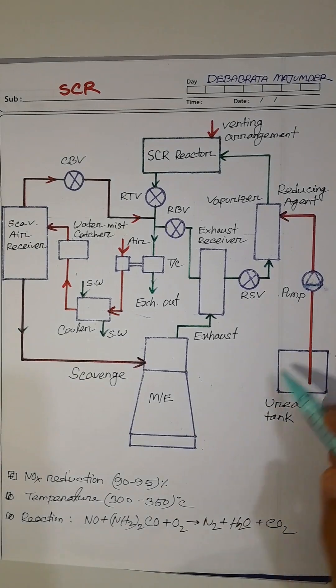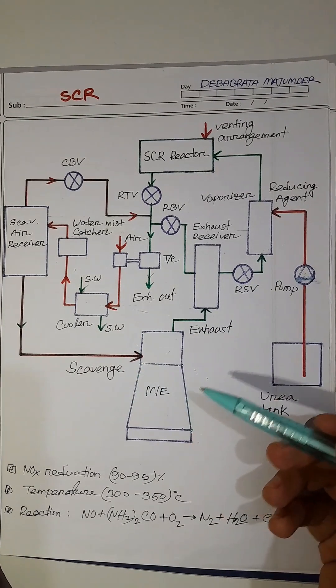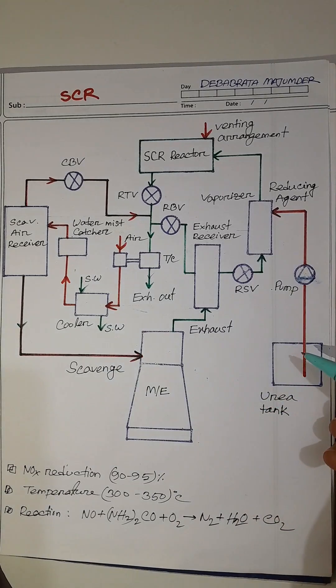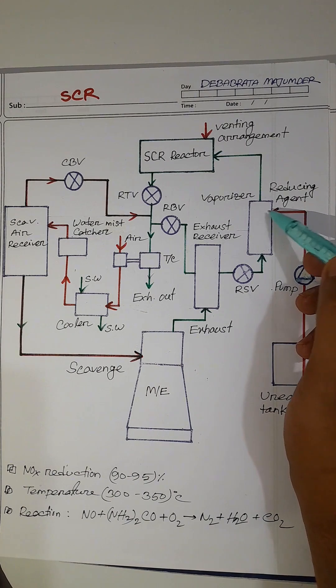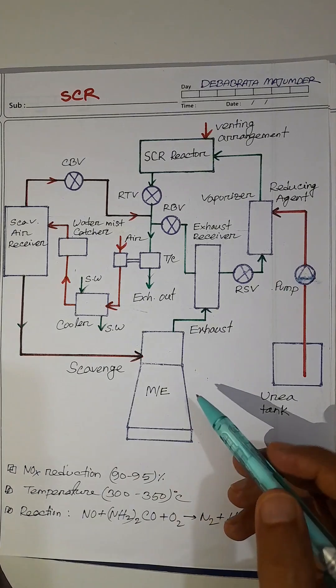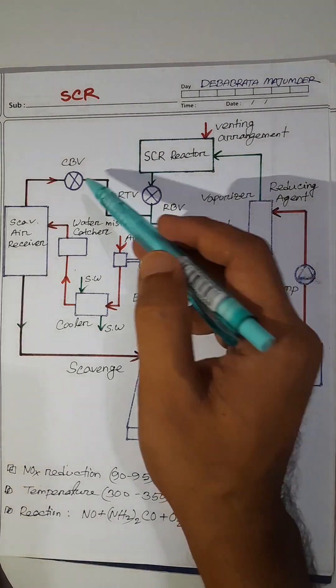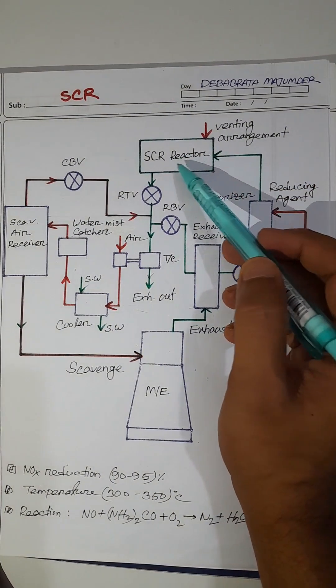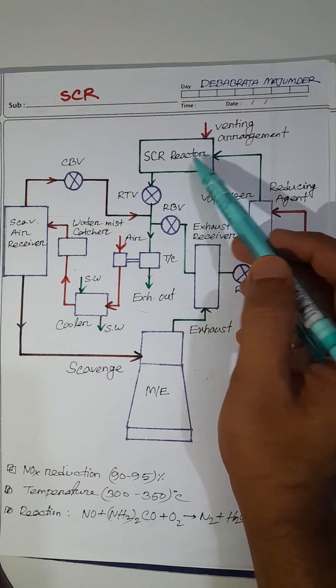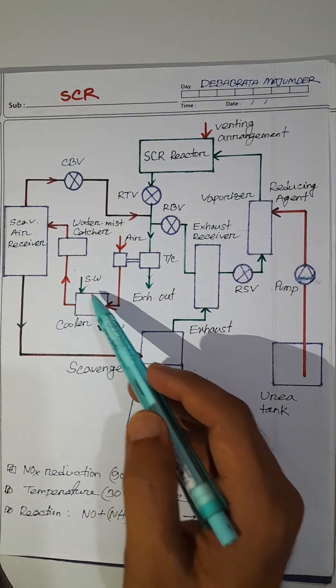In this system, the NOx reduction rate is 90 to 95 percent. Maintenance jobs include: weekly cleaning of the liquid filter fitted in this line; monthly checking of injector performance; monthly checking of each component like the vaporizer unit and valve function; replacing the catalyst element inside the reactor; and cleaning the cooler of the scavenger line at regular intervals.